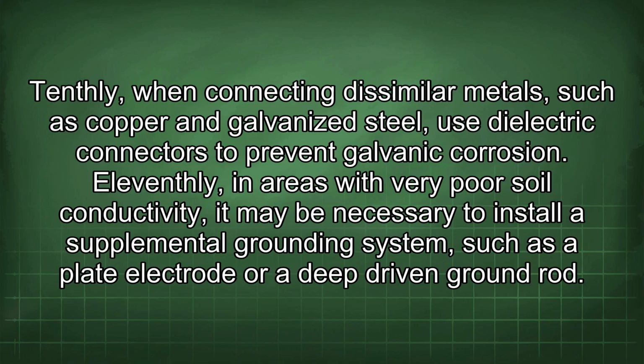Tenthly, when connecting dissimilar metals, such as copper and galvanized steel, use dielectric connectors to prevent galvanic corrosion. 11thly, in areas with very poor soil conductivity, it may be necessary to install a supplemental grounding system, such as a plate electrode or a deep-driven ground rod.